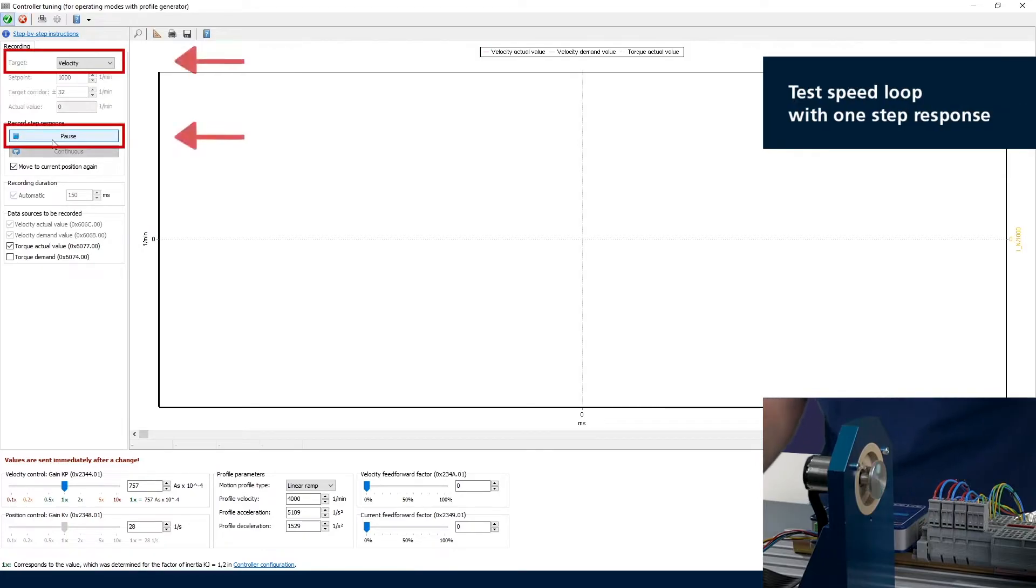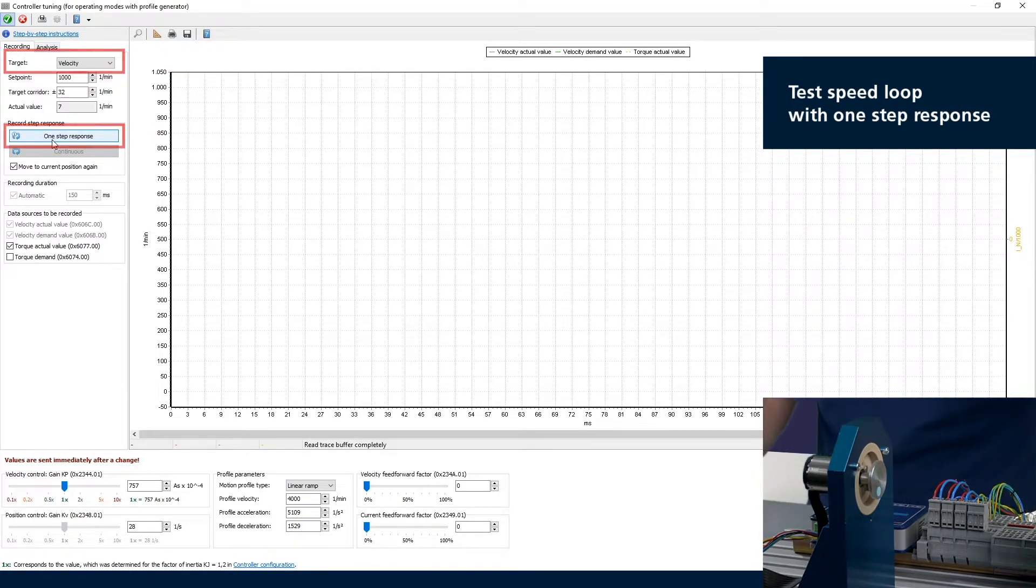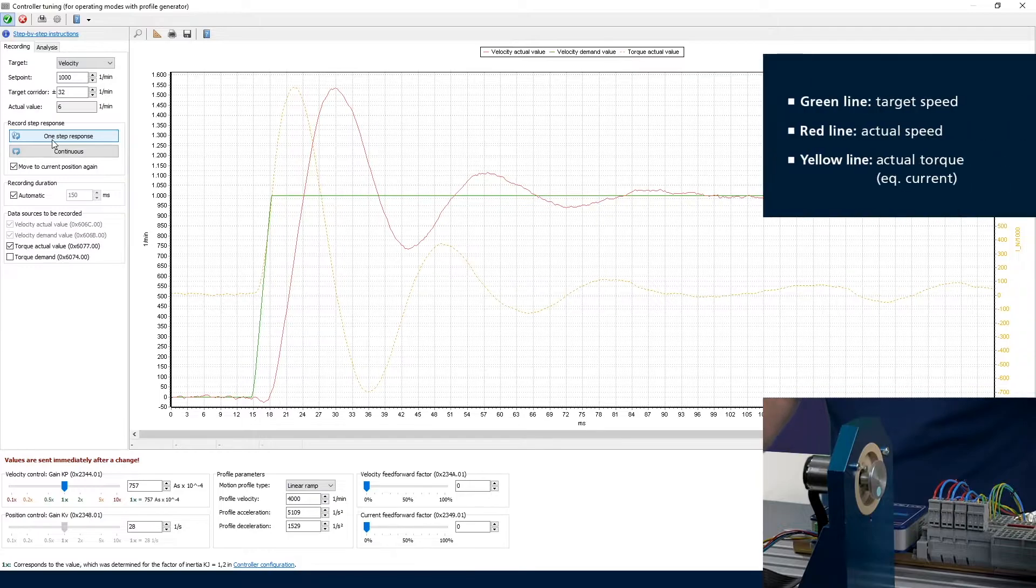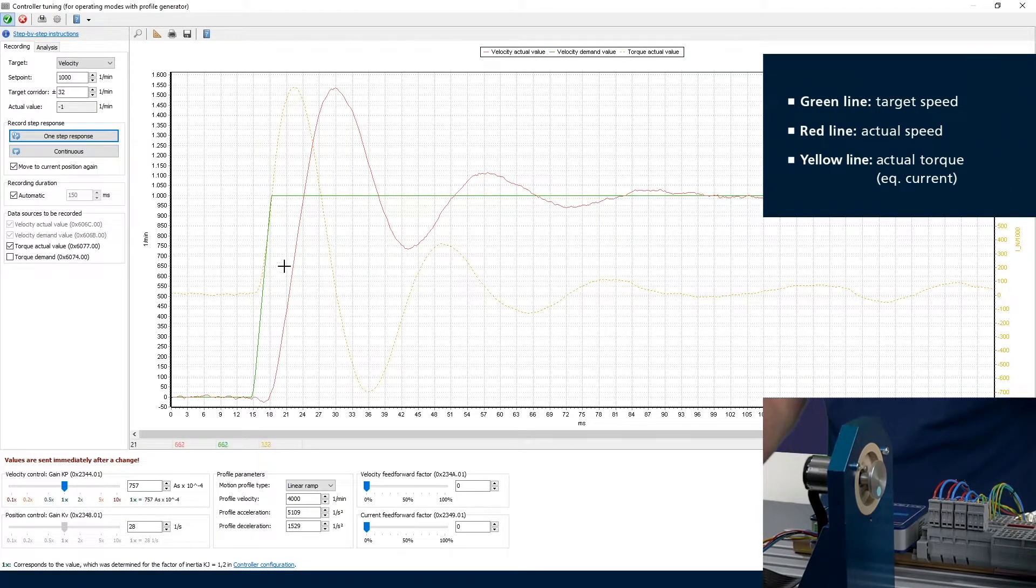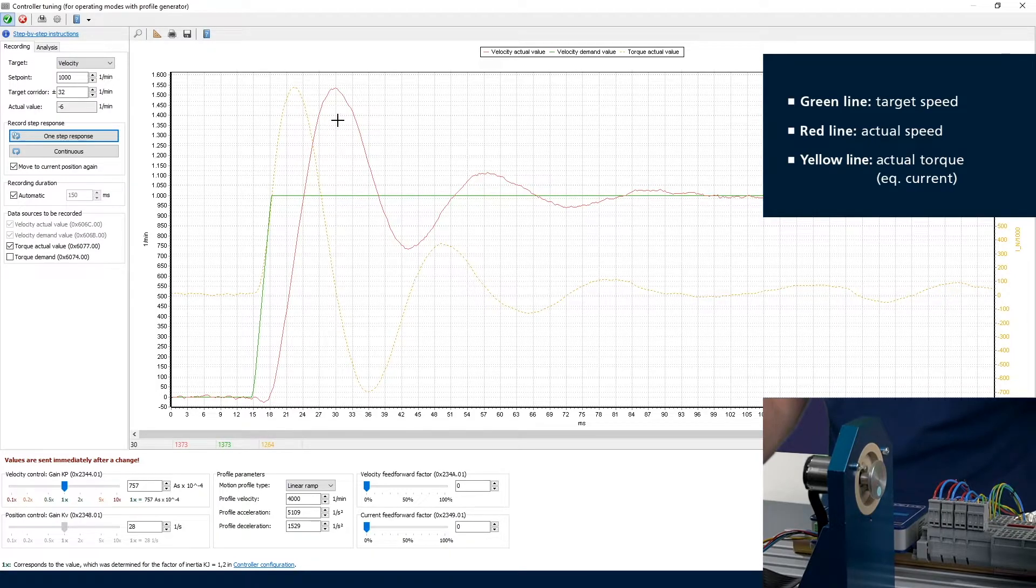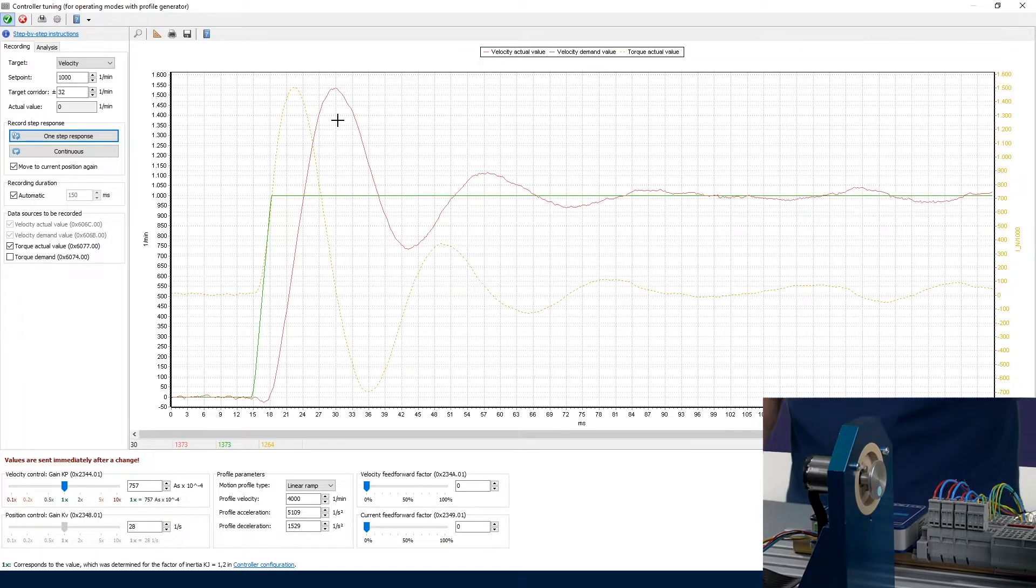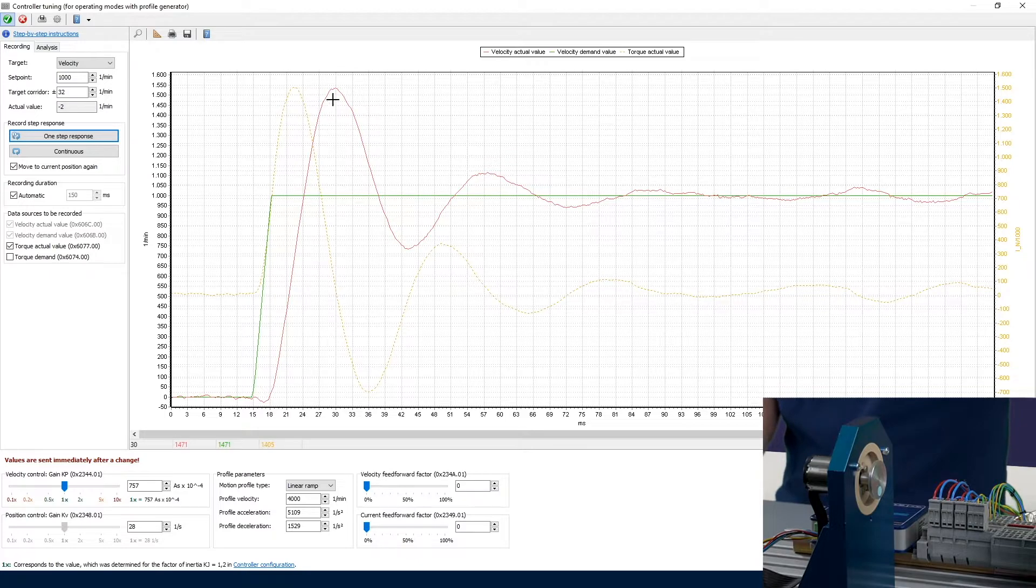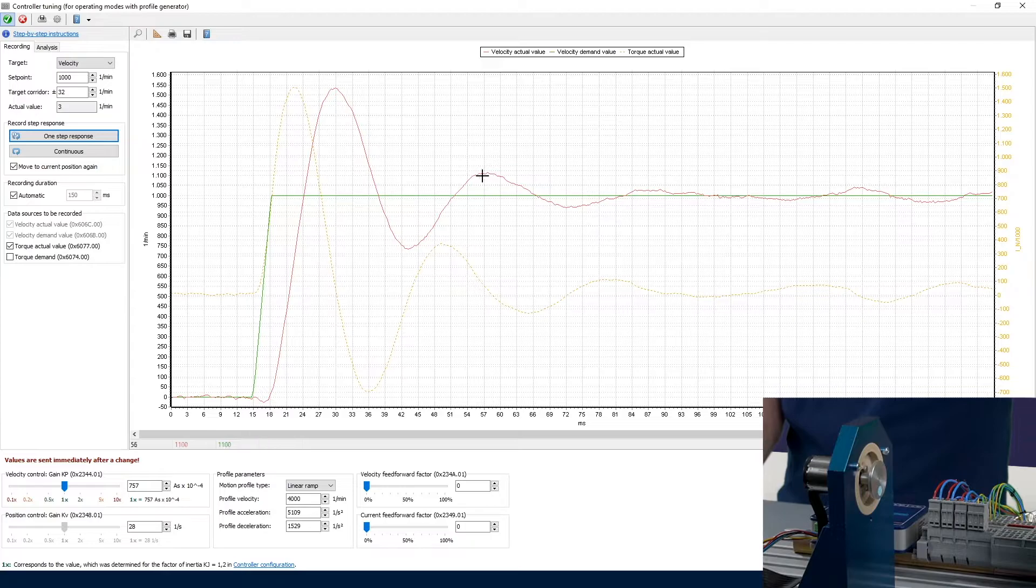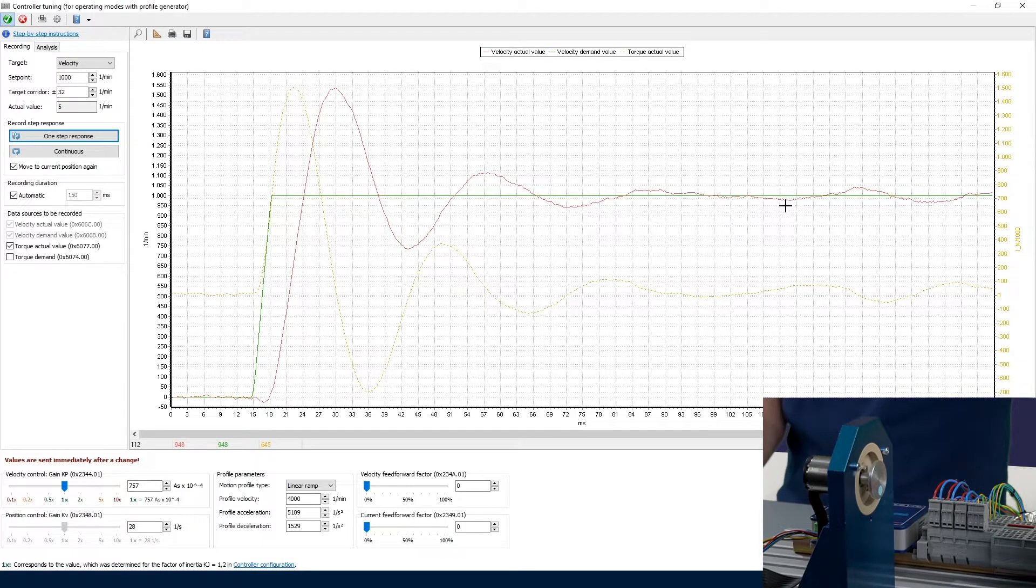Let's do a first step here. What we see is the green line is the target speed and the red line is the actual speed, and that's more or less like out of a textbook for this symmetric optimum of a speed loop, where you got an overshoot of roughly 40 percent when applying a single step, and then afterwards it's stable, so it's really coming into the corridor, but it takes some time.